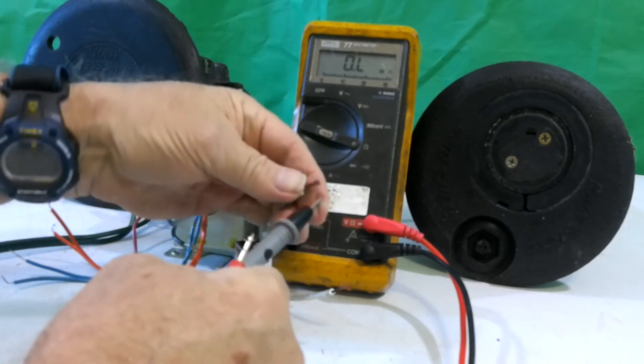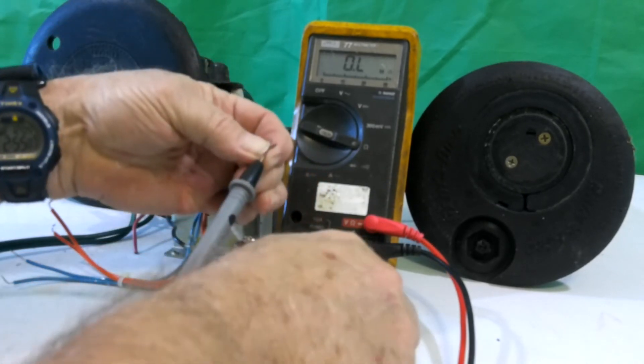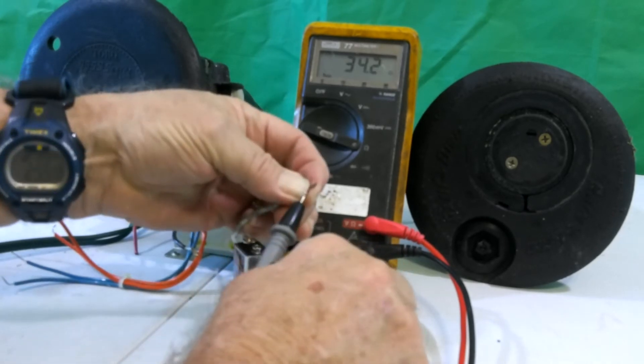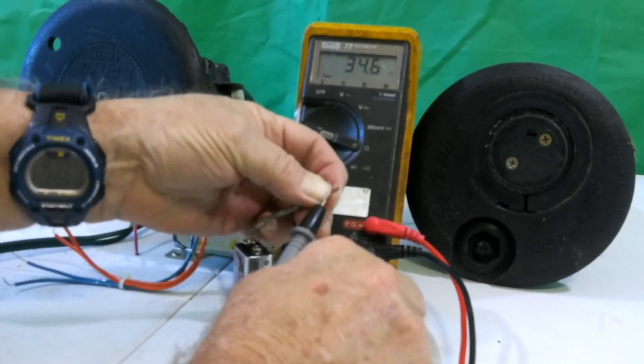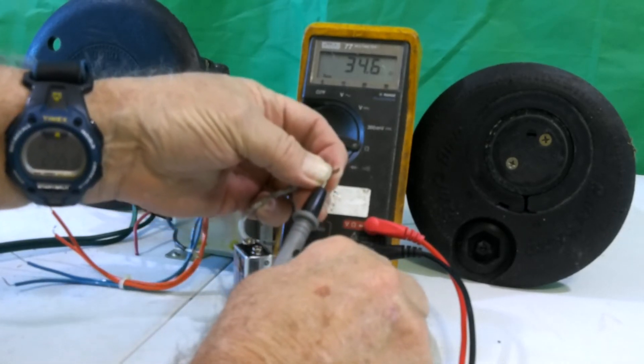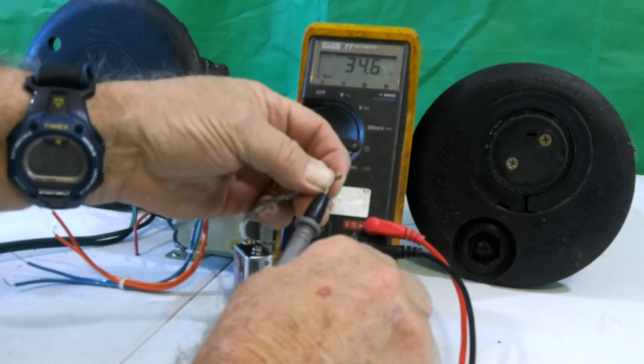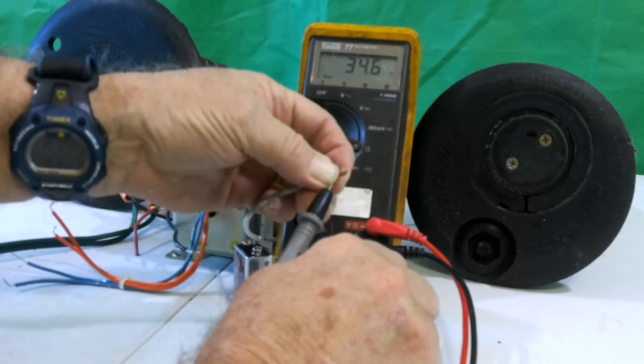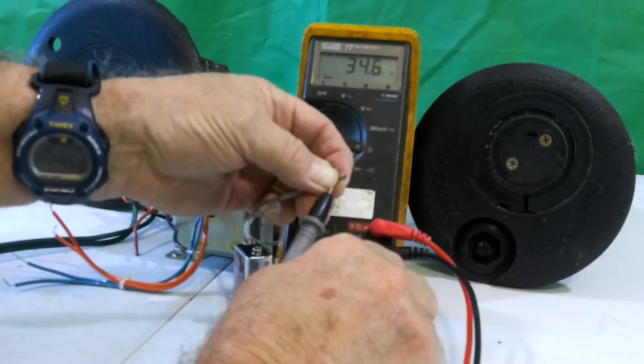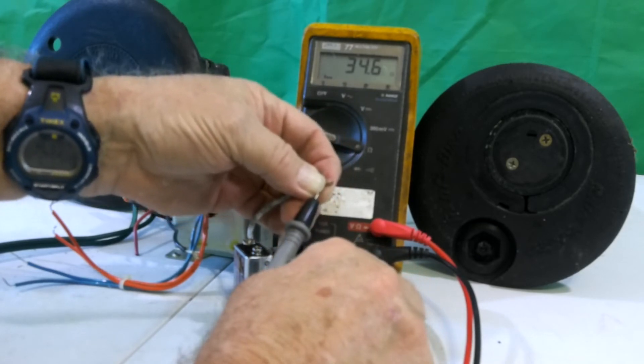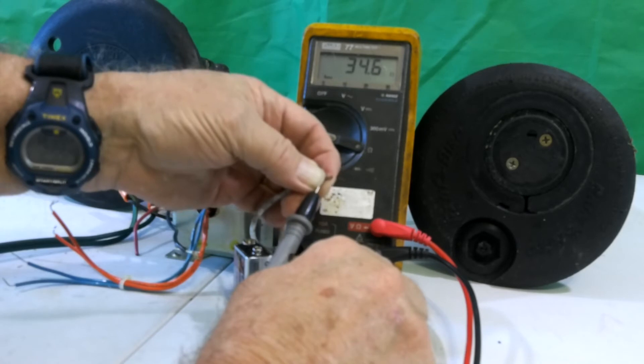Now I'm going to hook up to the Rainbird solenoid. And that's showing me a resistance reading of 34.6, which is a correct reading for that particular solenoid. So again, you need to know what solenoid is, what manufacturer, so you know what that resistance reading should be.